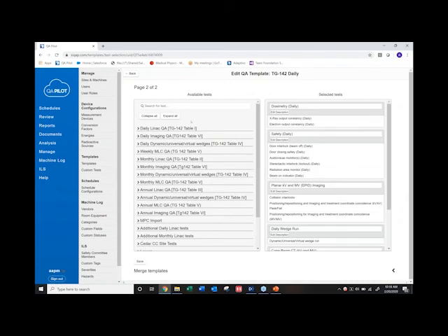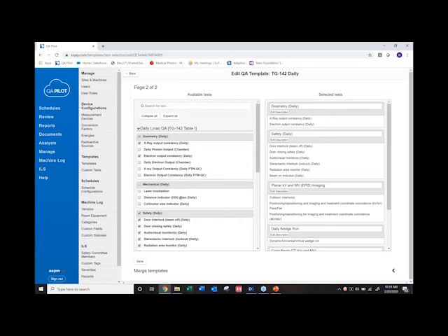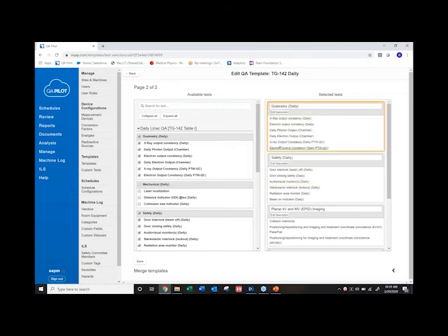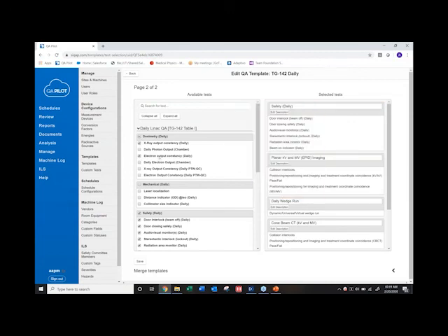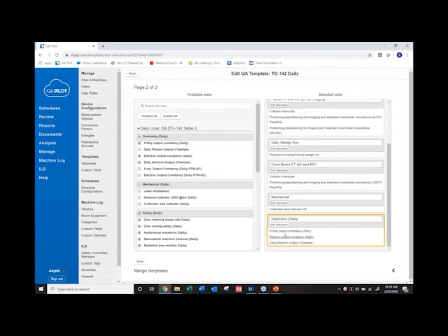So what we did was we started with literally every test that's in TG142, and those are available tests here on the left. And then it's a question of simply selecting what you actually want out of this entire list of TG142 tests that you want to do on a daily basis. Right now we have 2 from the daily dosimetry. If I click the box up here, it's going to automatically select all of them. Or if I've got these daily ones checked, but say there's something in particular that I also want to check with a chamber instead of my beam checker, my beam checker plus, then I would want to do that here. Anything that's been added is added down here at the bottom. Any additions to an existing template are automatically added to the bottom.